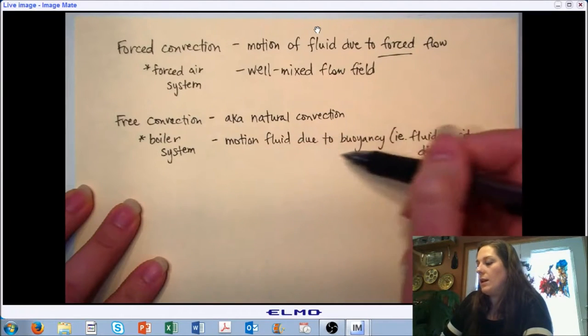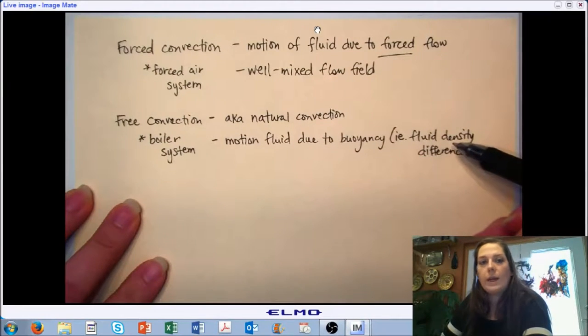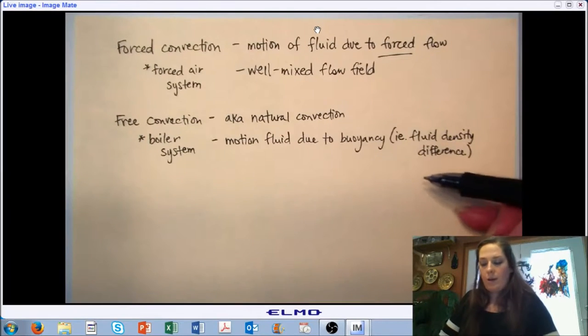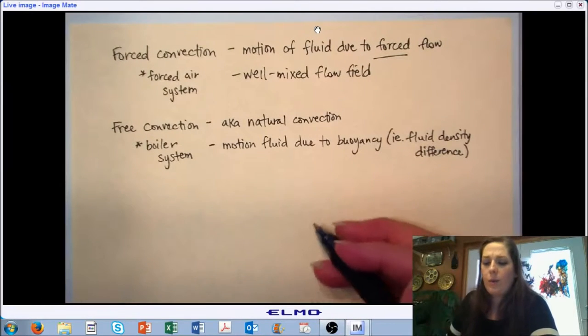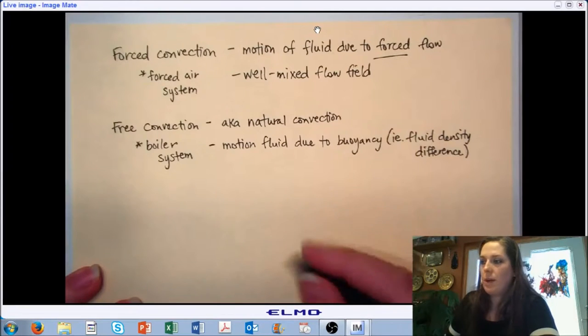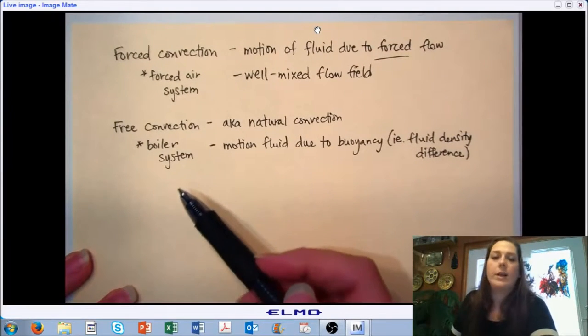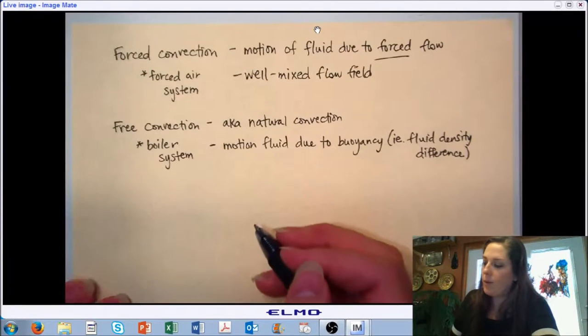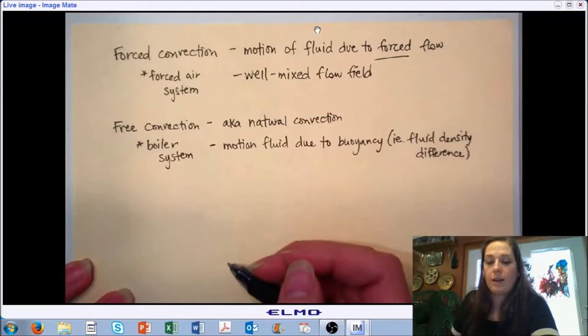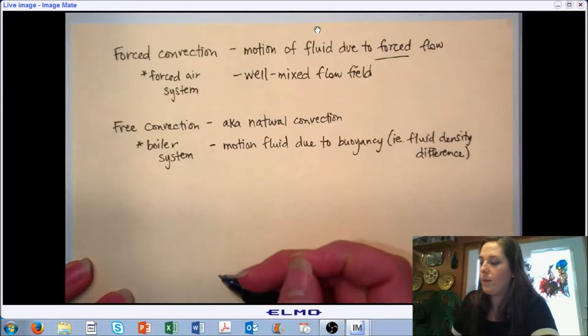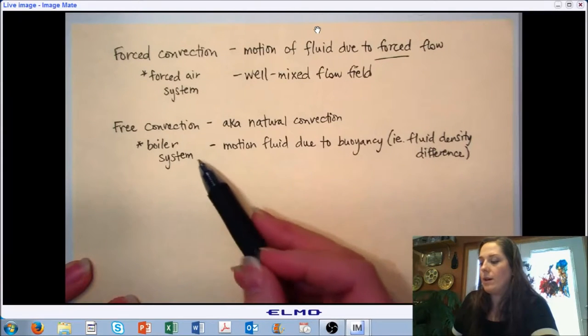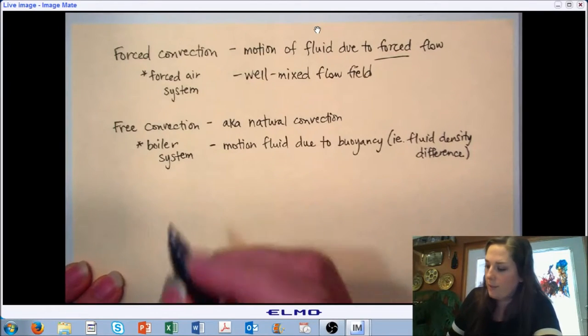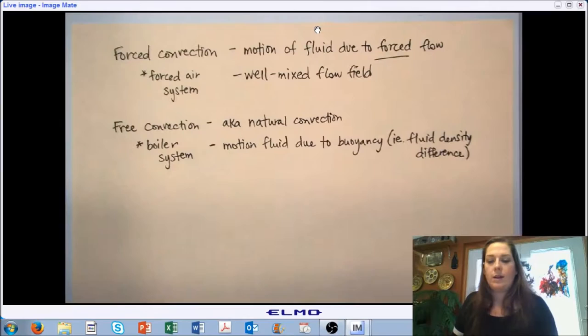The surface of a wall inside a building is primarily free convection as opposed to forced convection. Where we get our film coefficients — we referred to Table 5-2A, which is for a wall section for either inside or outside of the building. But we may have other instances where we're interested in convection, such as with our duct system as we're delivering conditioned air into a space. This is one of our primary opportunities for convection to have effects on our environmental control system.